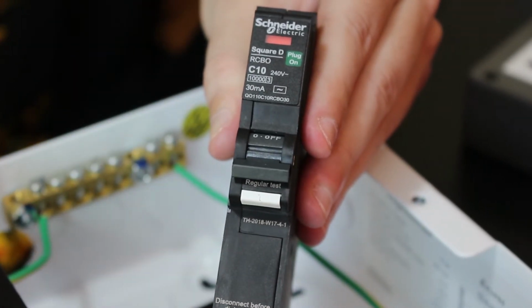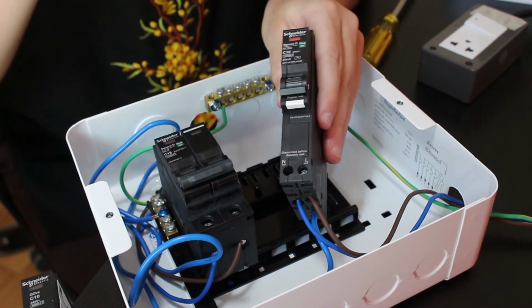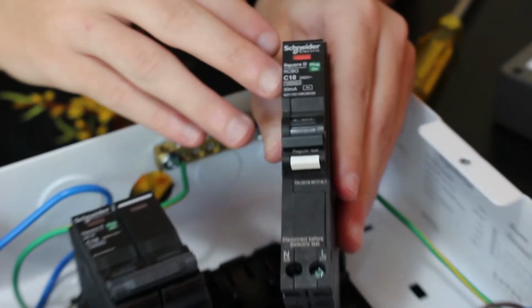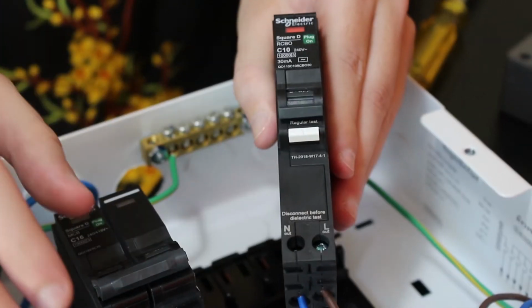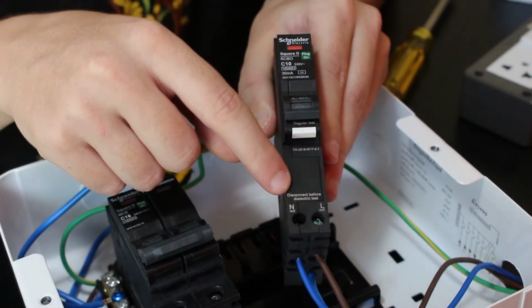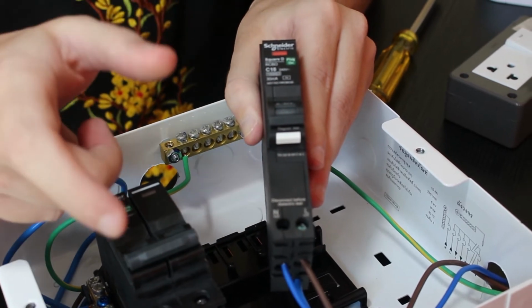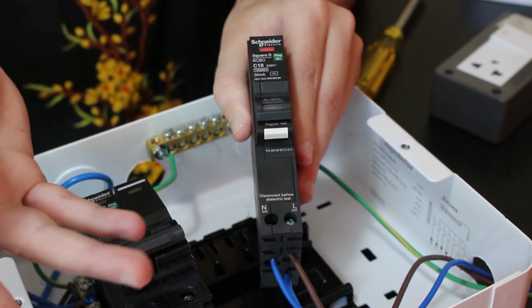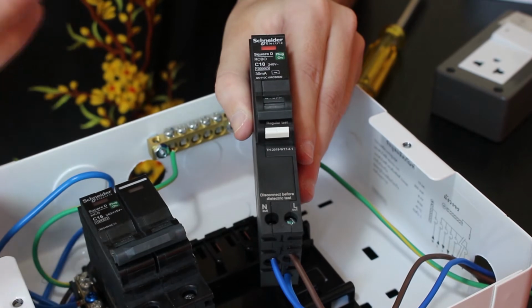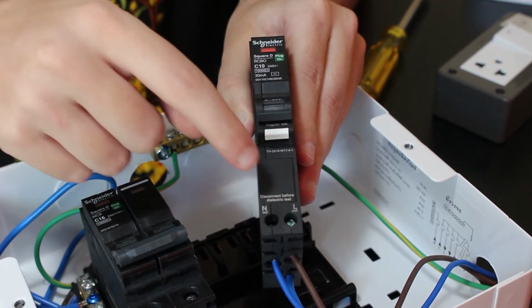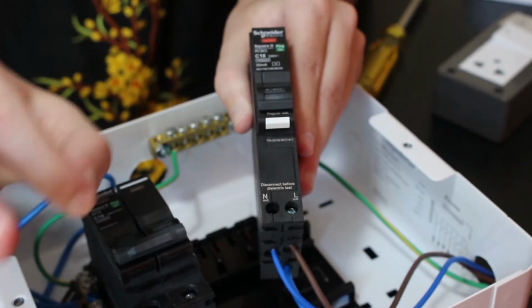The way an RCBO works is that it's going to measure the current going through the line and coming back through the neutral, and it's going to measure the difference between those two. If the difference of current is 0, that means all the current going out through the line is coming back through the neutral, so everything is fine.